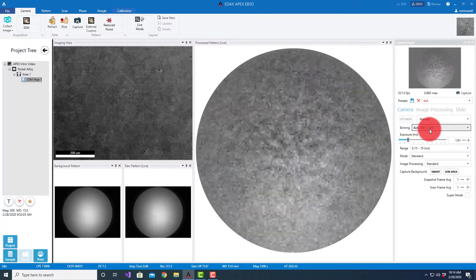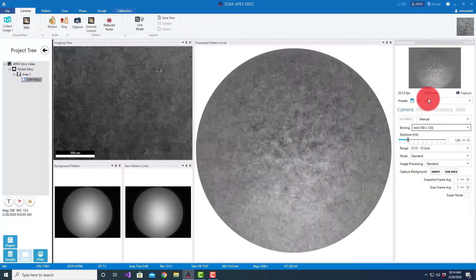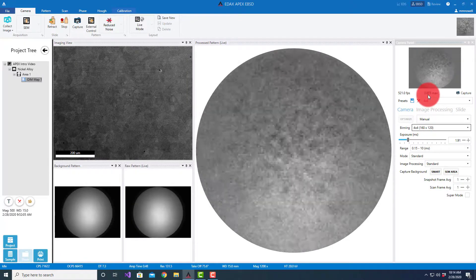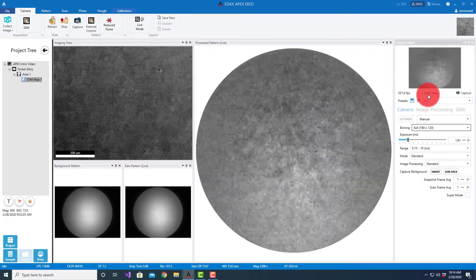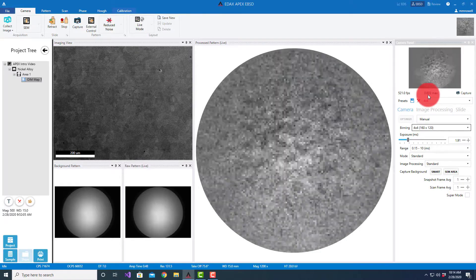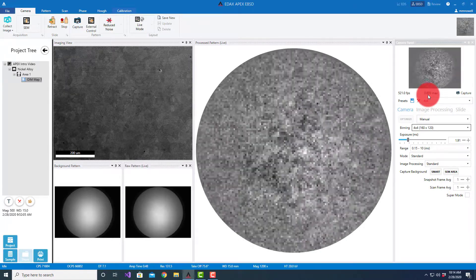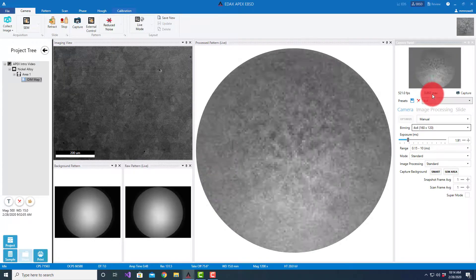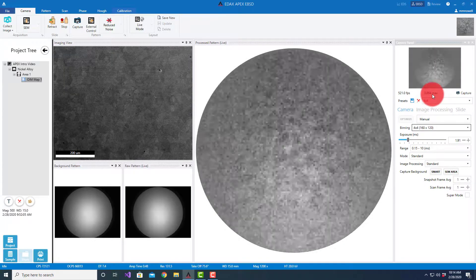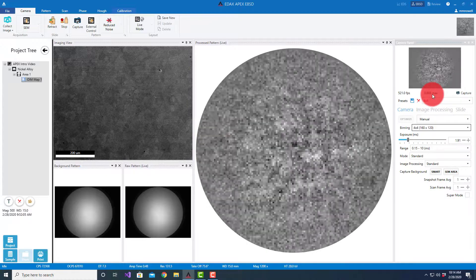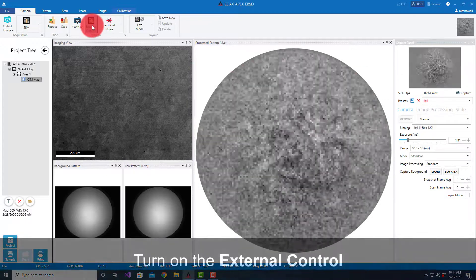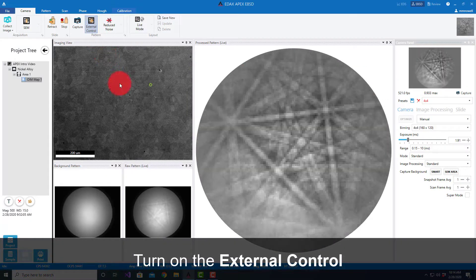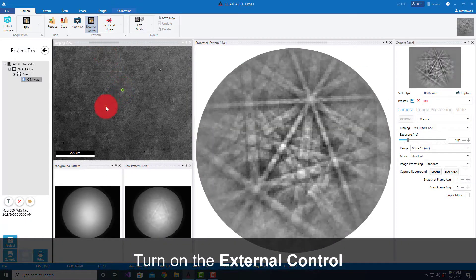When we've selected reduced noise, basically what we've done is selected a 4x4 binning and adjusted the exposure time to give us a maximum saturation value here at around 0.9 or 90 percent of the full well value of the detector.